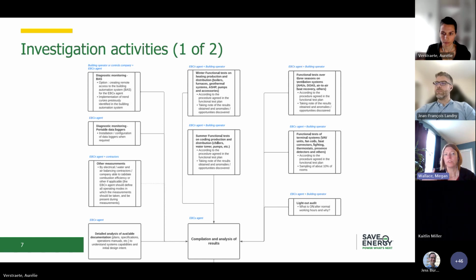They will then move on to do functional tests, and the functional tests will be done seasonally. You'll do a winter functional test and a summer functional test, as well as functional tests through all three seasons, so winter, summer, and shoulder seasons. We would do those on the main pieces of equipment, chillers, boilers, air source heat pumps, things like that, as well as functional tests on terminal systems, so your VAV boxes, fan coil units, lights, thermostats, things like that. And then we'll also do an audit of, here it's called, the lights out audit. So what lights are staying on after normal operating hours and why are they staying on?